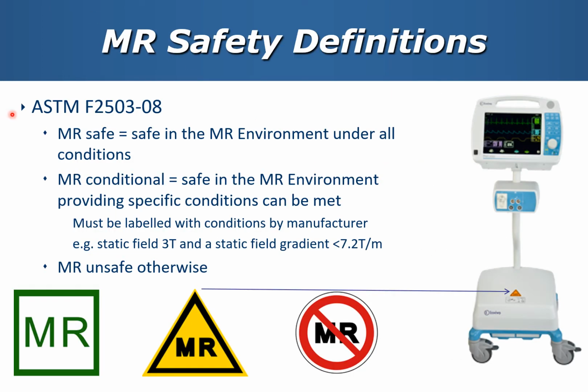Any equipment that needs to be taken into the MR environment needs to be labelled as either MR safe or as MR conditional, where the conditions for use can be met in that facility. All other items in the controlled access area which are potentially movable should be clearly labelled as MR unsafe. This patient monitoring system, for example, has an MR conditional label affixed to the base, dictating as to which field strength and which spatial field gradient it can be taken up to.